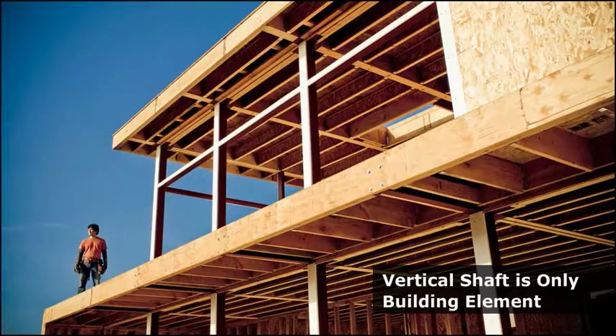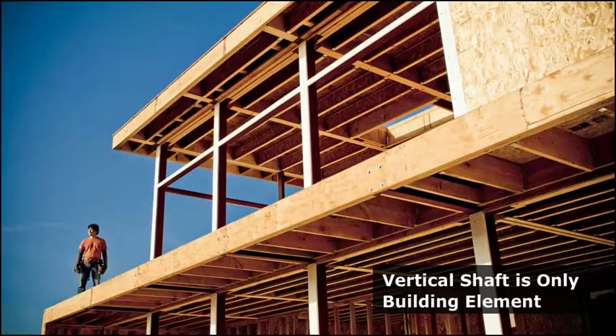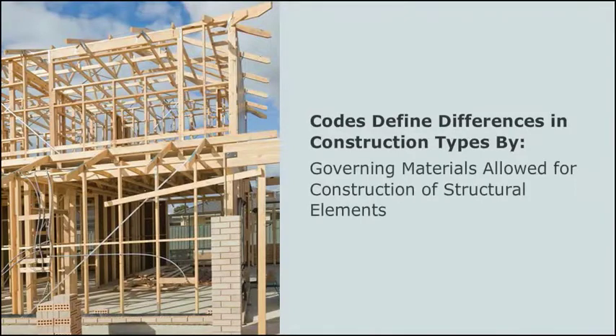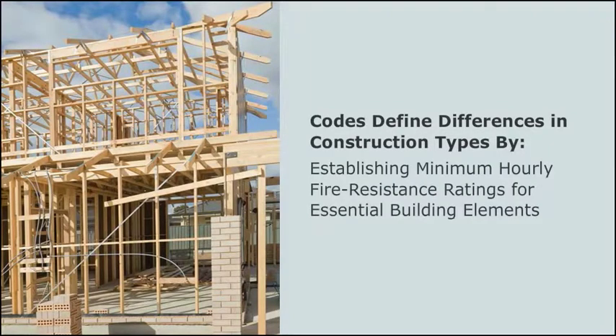Some of these elements are covered in the construction type chapters of the codes, and these requirements will be explained in this course. Additional elements are discussed in other sections of the codes. The codes define the differences in construction types by governing the kinds of materials allowed for construction of each structural element and by establishing minimum hourly fire resistance ratings for each essential building element.